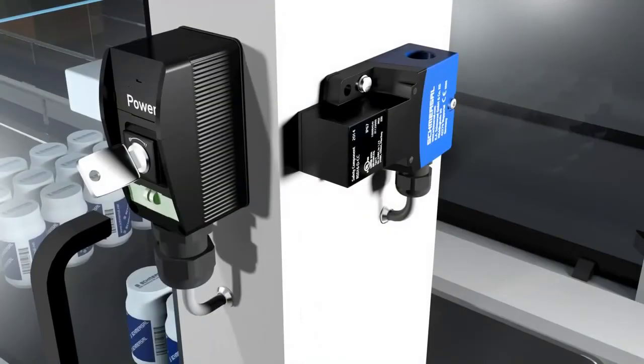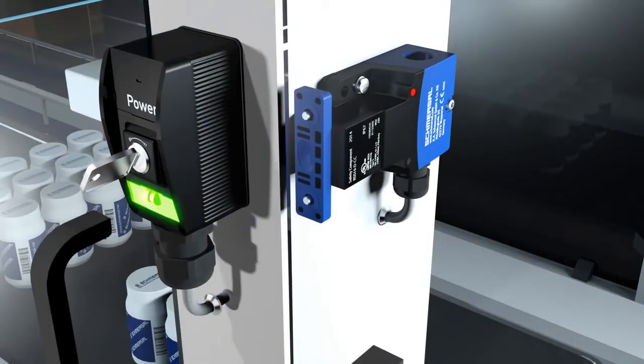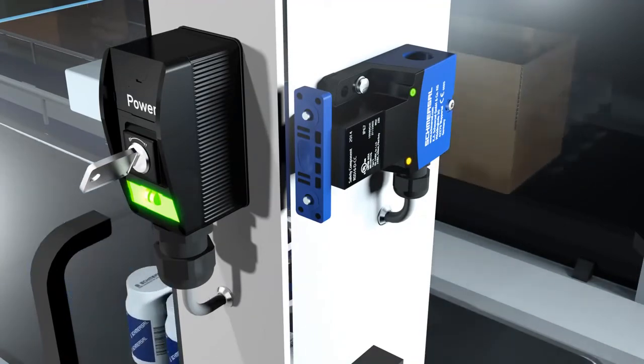Standard coded RSS16 units are operational in their factory delivery state. Individually coded sensors and actuators are very easily combined. First, the power supply is switched off, then the power supply is switched on again and the actuator is brought into the detection area. The teach-in process is signaled at the sensor with an illuminated red LED and a flashing yellow LED. After 10 seconds, short flashing impulses require the supply voltage to be switched off. The next time the supply voltage is switched on, the actuator needs to be acquired again to activate the taught activation code.